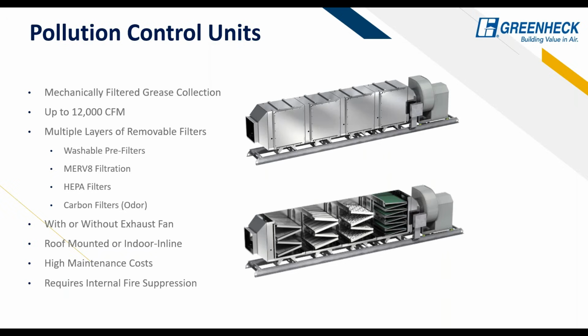So basically, what these are is just a large filter bank system, going through pre-filters, MERV8 filters, HEPA, and carbon filters for odor, and we can modulate these pretty well and provide three or four options, whatever you might need. These will also have their own fire system integrated, because these are filters and it is a grease application. So you'll have a fire system at the hood and you'll have a fire system here. There'll be independent fire systems, but they will be interlocked together. So if one goes off, the entire system will go off. That's something to keep in mind as well.